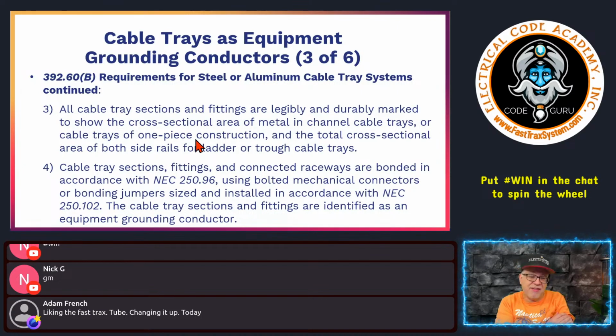The engineer didn't design it with equipment grounds because they were in a tight little pinch, so they designed it with a cable tray that was to be used as an equipment ground. But that's not what was ordered, and that's not what was installed. And when the engineer came out on a final walkthrough, which not all engineers do, by the way, they caught it. And at that point, there was an issue, okay?